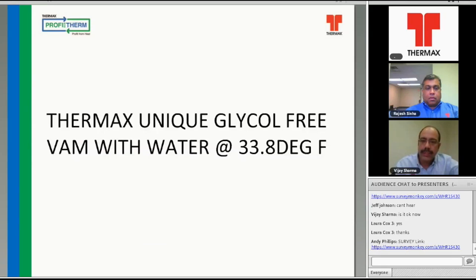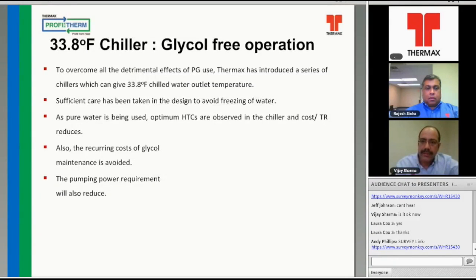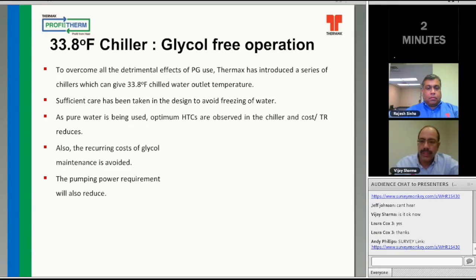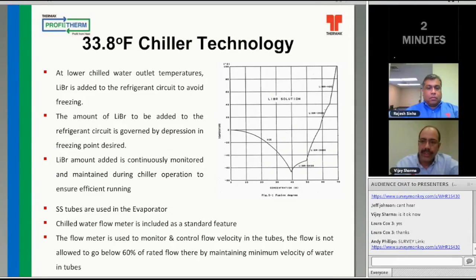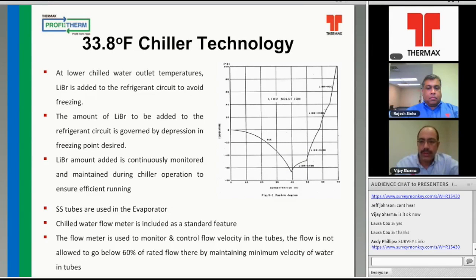And again, how 33.8 can be achieved in the regular standard absorber, how we are achieving that is what is being shown here. We are getting 33.8 by using the same refrigerant, but in most cases lithium bromide is not used for low temperatures because the refrigerant itself is water. So what we are doing here is to avoid the refrigerant itself becoming frozen. We are using lithium bromide as a solution to lower its freezing point, and that is why the refrigerant is not allowed to freeze, by adding some lithium bromide. So we are making it an aqueous solution, a brine, as a refrigerant, and that allows us to run the same absorber at lower temperatures.